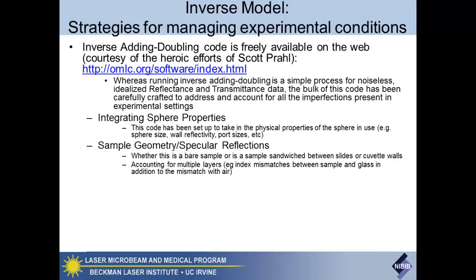This code also accounts for the sample geometry and specular reflection: is it a bare sample, what's the index of refraction of your bare sample versus air, any specular reflection in both transmittance and reflectance cases. Is it sandwiched between two pieces of glass, or in a cuvette? What are the optical properties of that cuvette, the index, the multiple reflections potentially occurring between the boundary between air, cuvette wall, sample, sample-cuvette wall, and inside the integrating sphere? It's been able to calculate all that stuff for you, which is a big headache to think about.